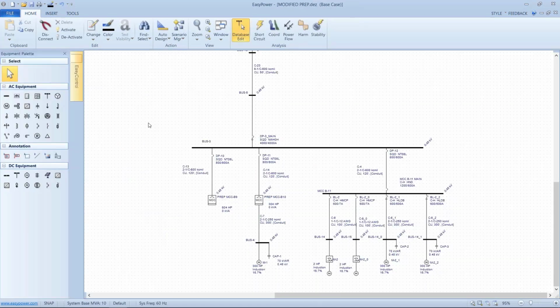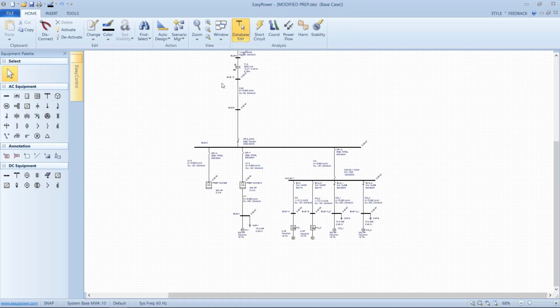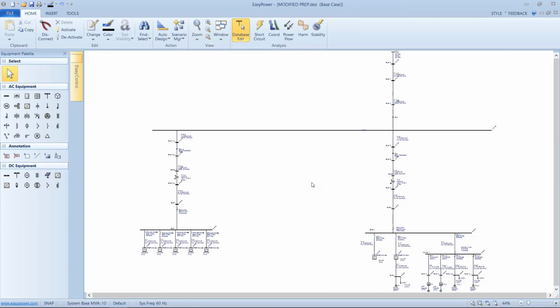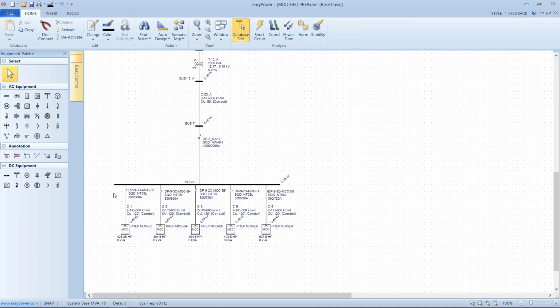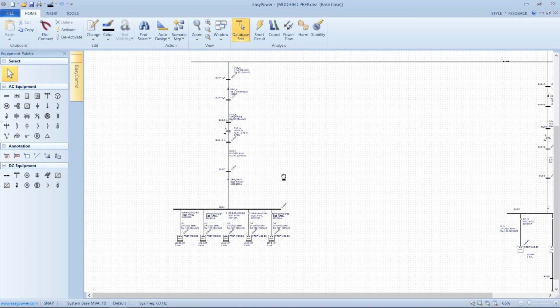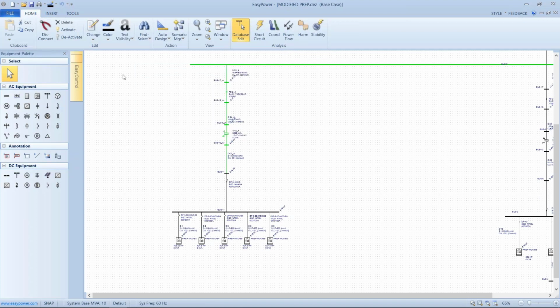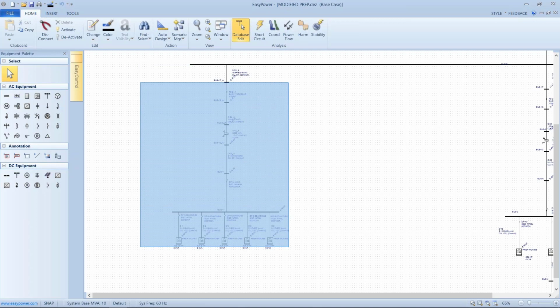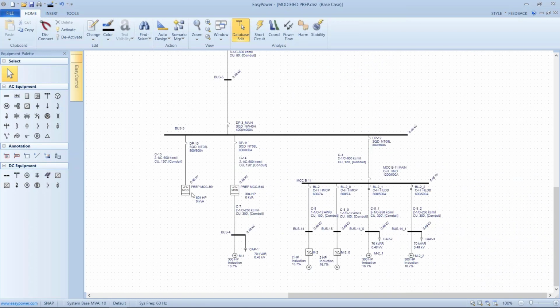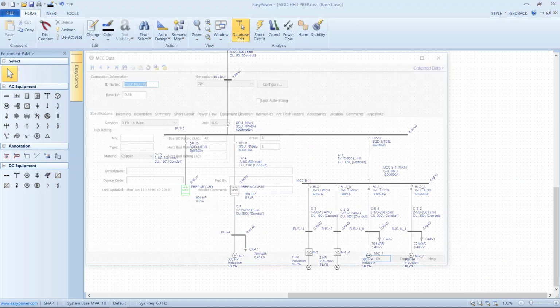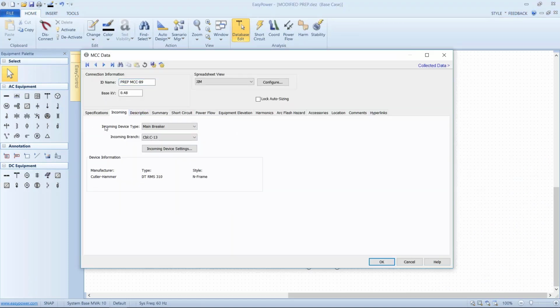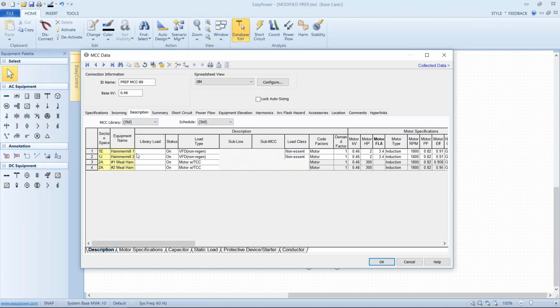And here's a system that we got. Actually, we had a number of, and if I go to the full blown, we'll see it was a much larger one-line diagram, and several of these motor control centers had some very large loads in them. What I've done is basically isolated one out, and as a result, I'm going to isolate this other side so it doesn't get in the way. And so now here's the example of our motor control center. If we open it up, you can see that we've detailed out the main, and in each of these cases we have 2 VFD loads and 2 motors with TCC.